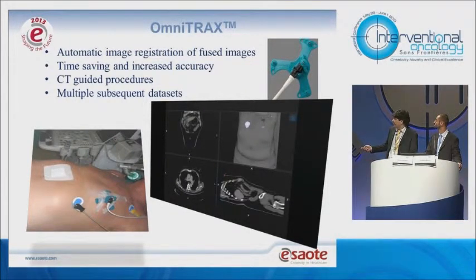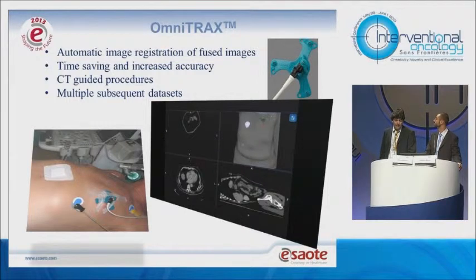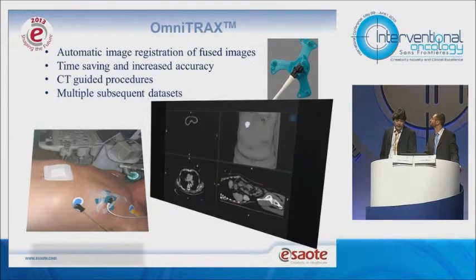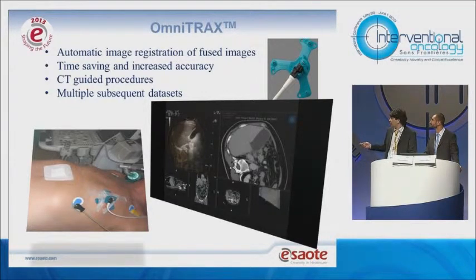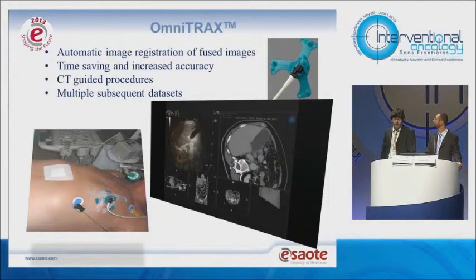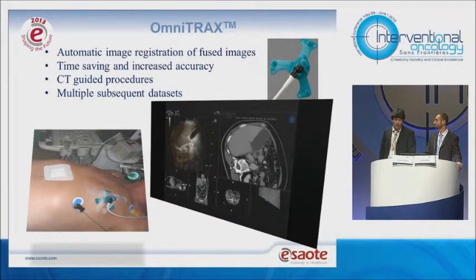Another way to register the patient with their dataset is to use an external device — an evolution of the external marker — into which we can directly plug an electromagnetic sensor. Once the device is identified in the dataset, with one click it is possible to register the data. This is particularly useful for CT-guided procedures, where more than one dataset is needed to assess needle position without real-time ultrasound imaging.